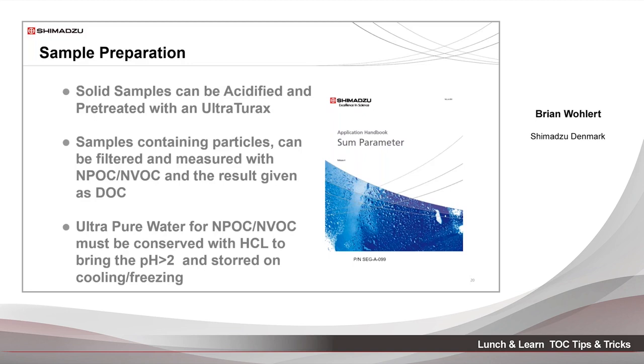It's also possible to measure samples containing particles. Sometimes these particles have to be filtered to do the NPOC or NVOC analysis. You have to keep in mind that you do not get the TOC value when you filter your sample. Then you are actually measuring the dissolved organic carbon.